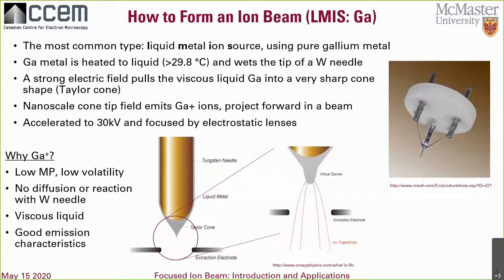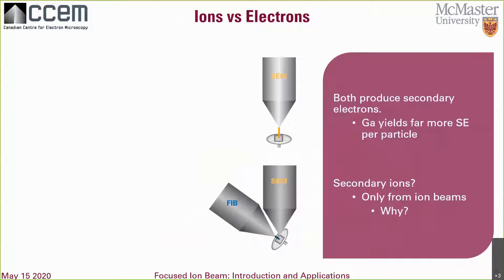There is good reason why gallium is typically the ion source of choice for FIB. It has a low melting point, only about 30 degrees. Minimal reaction or diffusion between the gallium liquid and the tungsten needle. It has low volatility so it keeps its source reservoir from evaporating. The emission characteristics provide a small energy spread because most nearly all of the ions come off as one-plus. Like electrons, when gallium interacts with the specimen it also causes secondary electron emissions, actually a lot more than electrons do.